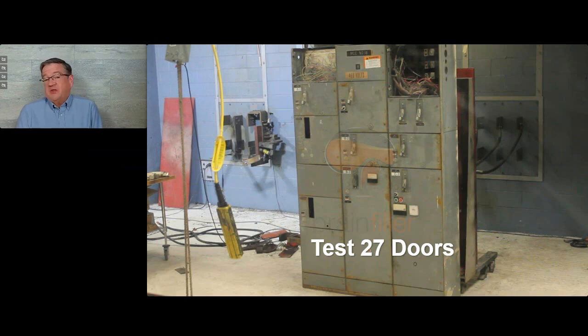And the door does not offer protection. Yeah, I have a keen perception of the obvious. What it was, just the pressure, you don't know. Depends on the type of equipment. There is arc-rated equipment or arc-resistant equipment that's designed for the doors to stay closed, but that's a special design. I had another one, tested a motor control center, and you'll notice the upper corners, the doors are off. So you think, okay, pressure relief. Well, let's take a look at what happens here.